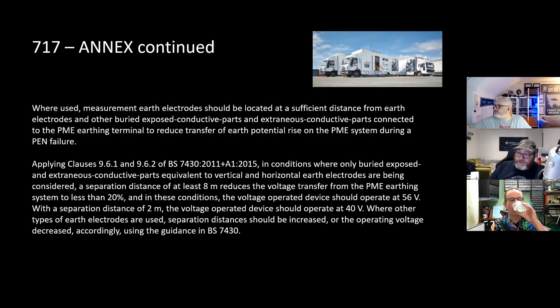This is really where changing an existing installation to TT is next to impossible, certainly on domestic and smaller properties, because if you're looking at distances of 8 meters, that's probably going to be impossible on a very large number of properties, because your 8 meters puts you in next door. So you just can't do it. And there's a comment actually from Wayne, I think it was, it's gone off the screen, but said it was looking like everything's going to end up as TT. Well, some things are going to end up as TT, others are going to end up as TNCS with separate foundation electrodes.